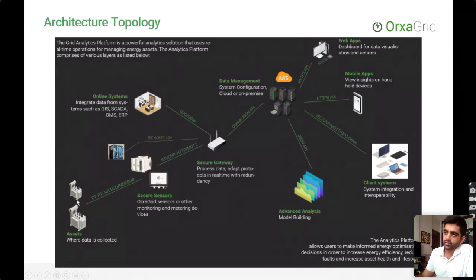In terms of data acquisition, on the bottom left, we can see that there are different ways. So the assets, which are your substation, transformers, circuit breakers, it could also be pole top distribution transformers or feeder pillars, which are available on the sides of the roads, or any other grid node, which is a measurement point. So any measurement point on the electricity infrastructure, typically the most basic ones that are inputs from your CTs and PTs to get the current and voltage measurements. Once you get CT PT input, you can calculate all your energy metering parameters, power quality parameters, and all of that. So the first two inputs are CT PT.